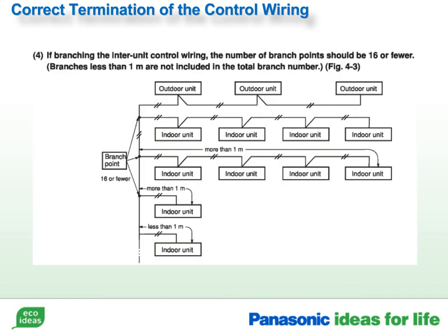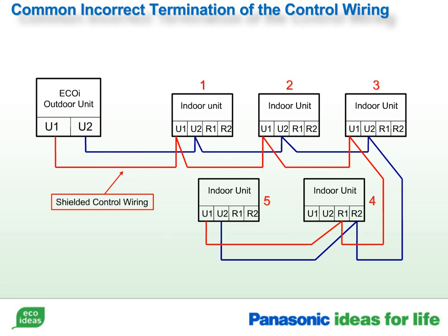The branch method is also acceptable, however, the daisy chain method is recommended. It's much easier to find a break in the wiring if you ever had such an issue, and has less restrictions than the branching method. This example shows one of the most common wiring mistakes. R1 and R2 are the remote controller connections.